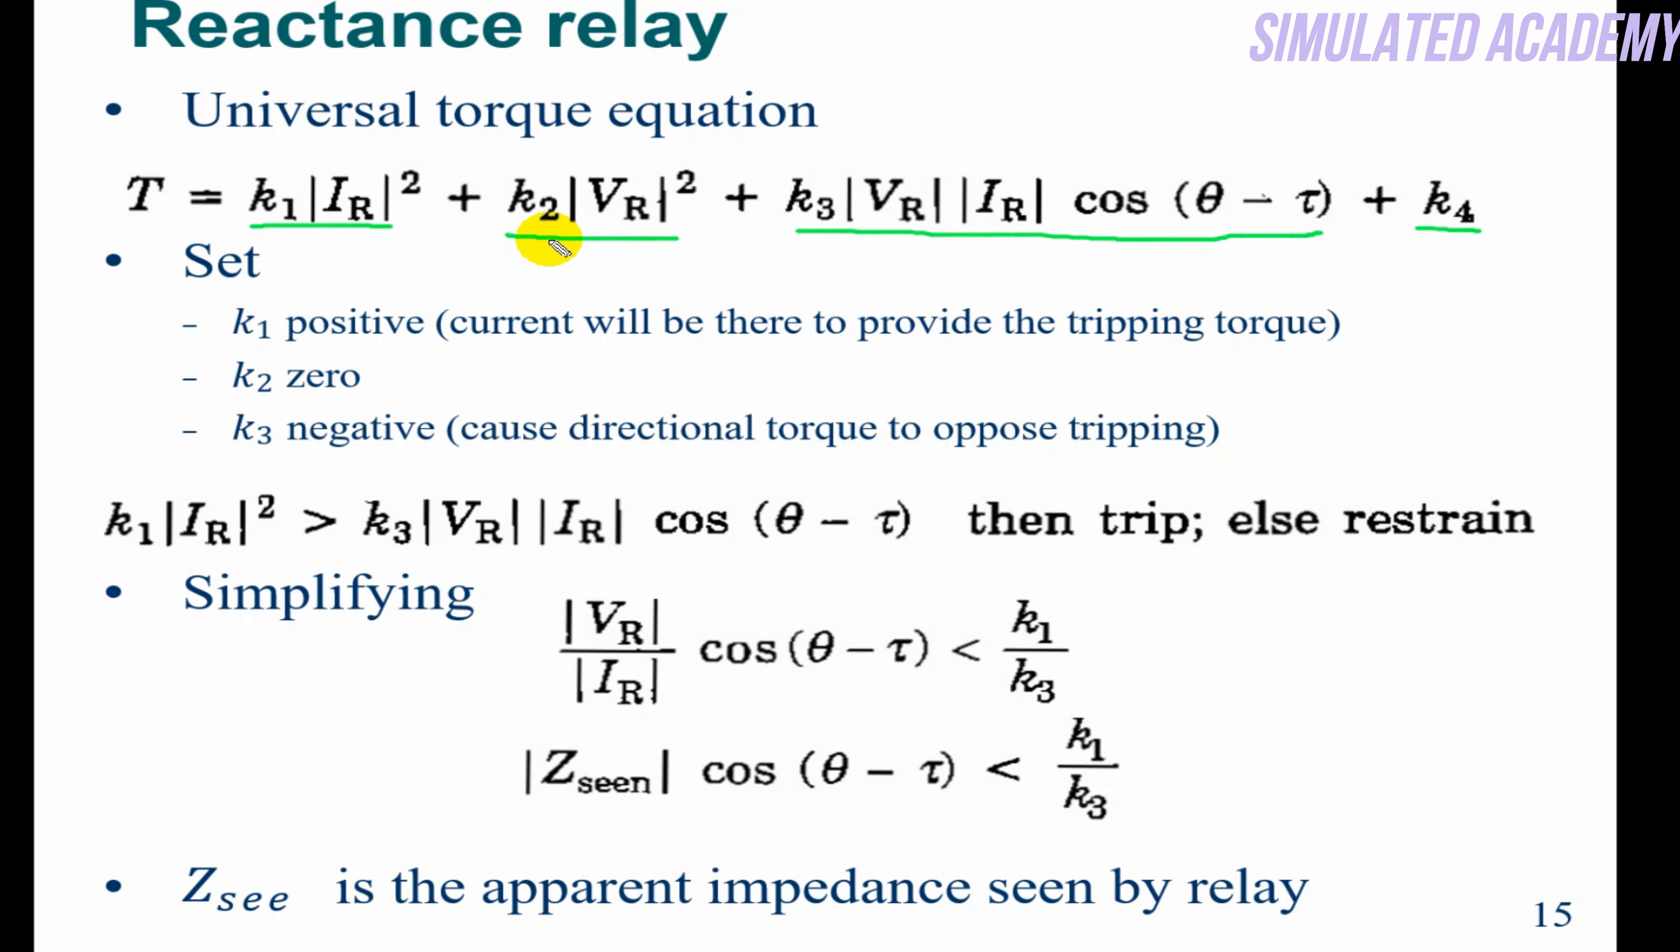For the reactance relay, the universal torque equation can be arranged such that k1 is positive, meaning k1 will act like an operating coil providing operating torque causing the relay to trip. k2 we set to zero, so there is no torque because of voltage. k3 we make negative, and it will be smaller than k1—this is restraining torque. So if k1|IR|² is greater than k3, this is the trip condition; otherwise it will remain restrained.